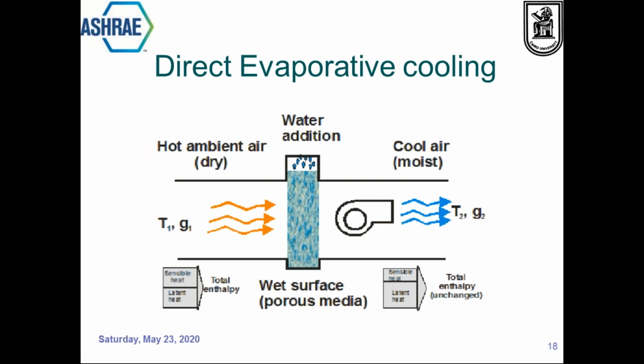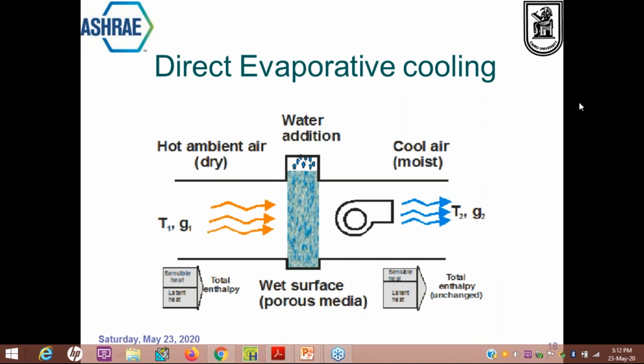The first question asks how much the set point for RH should be, and which one is more efficient, direct or indirect cooling system. Thank you very much, a very good question. The direct evaporative cooling is very useful, but the indirect evaporative cooling is more effective in this case.